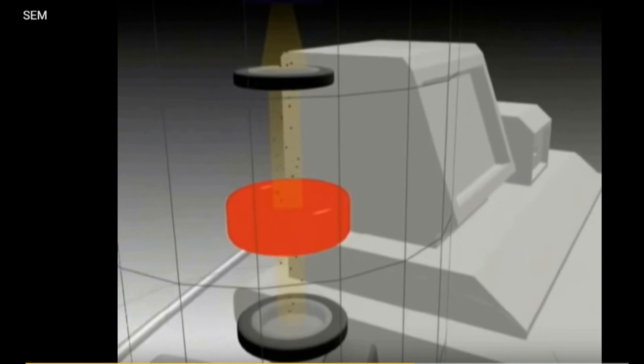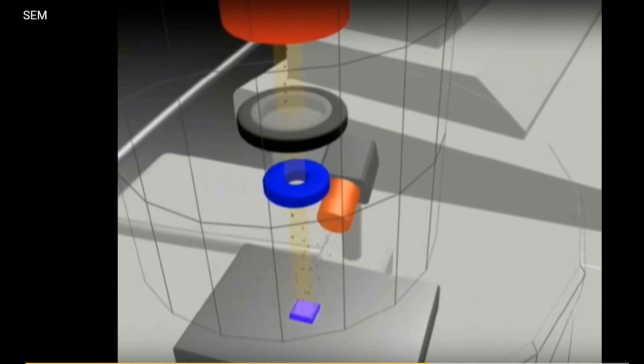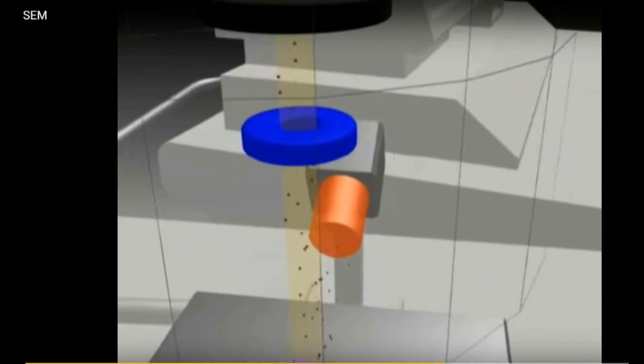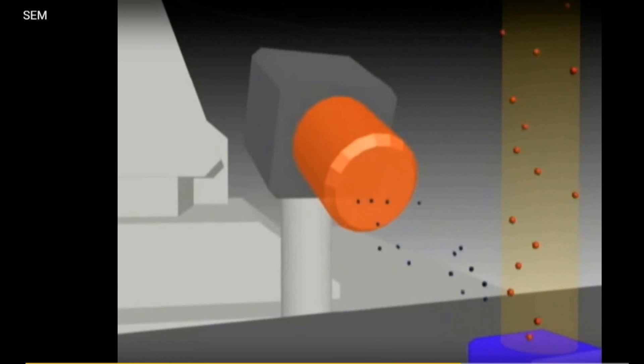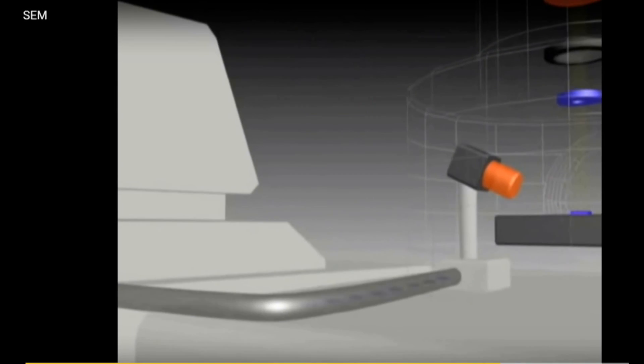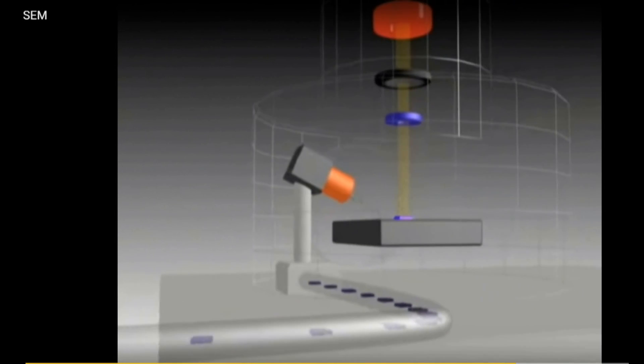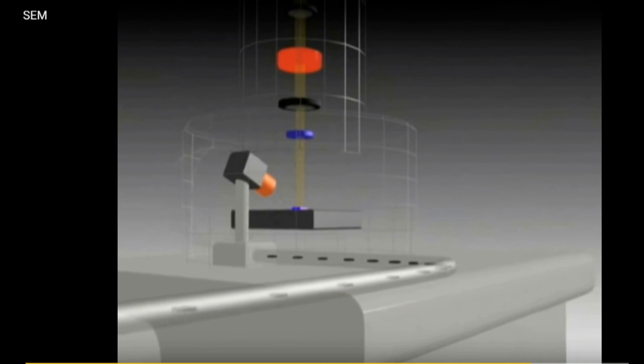The primary broad diverging beam is concentrated by a series of magnetic lenses to focus finely on the specimen. At the point of incidence, primary electrons knock out the electrons of sample material. These knocked out electrons are called secondary electrons, which are collected by the SE detector.